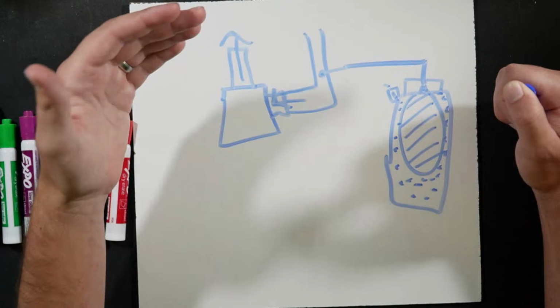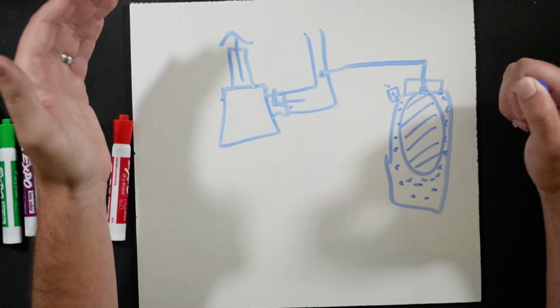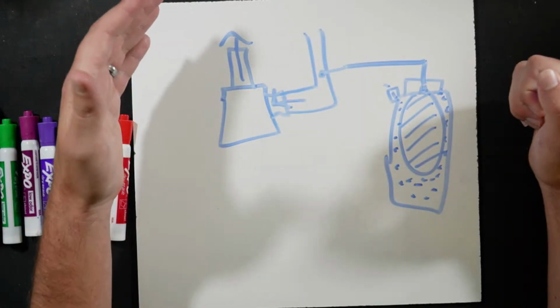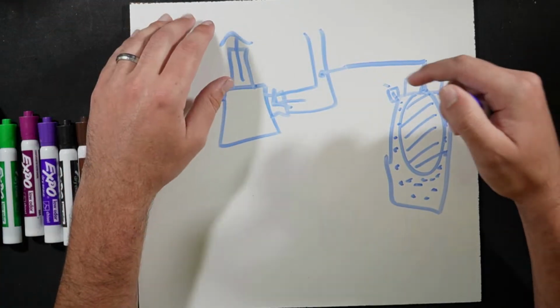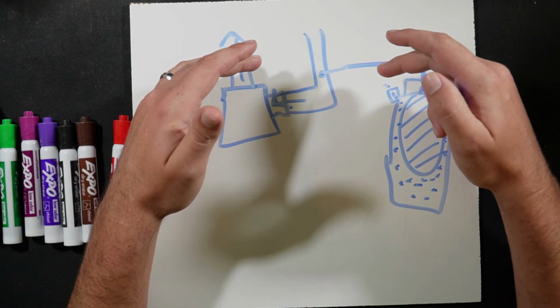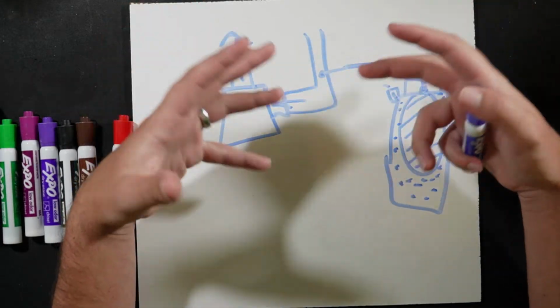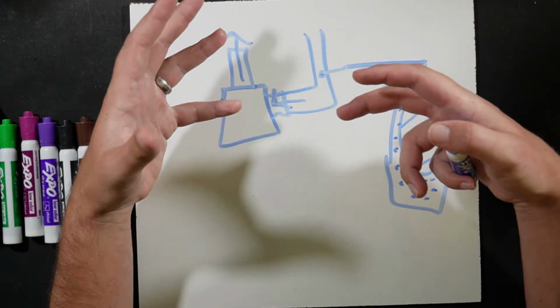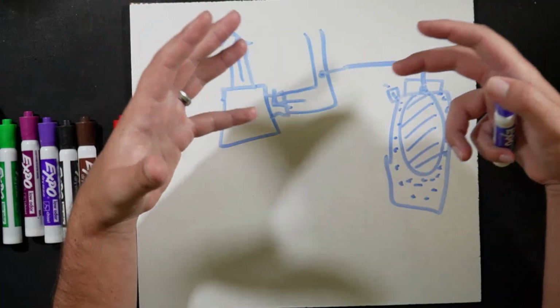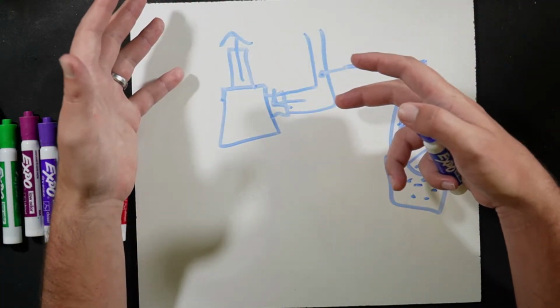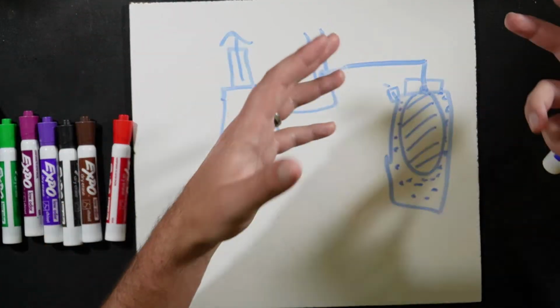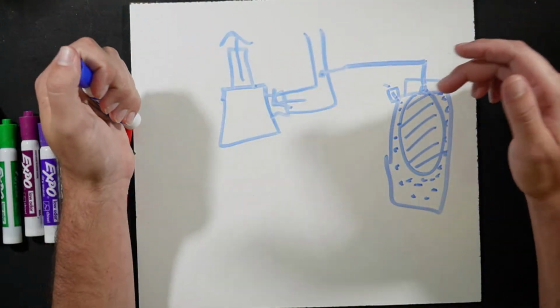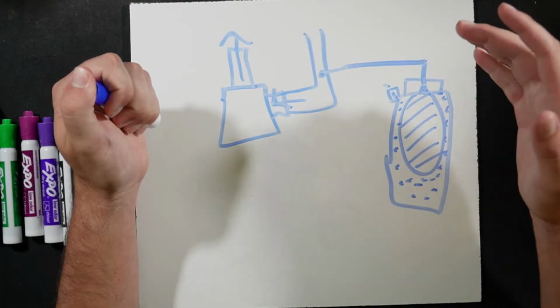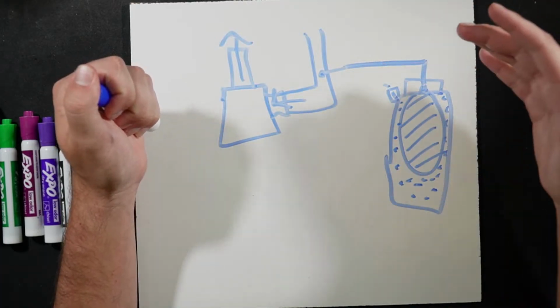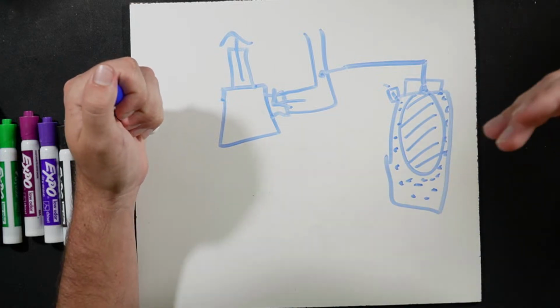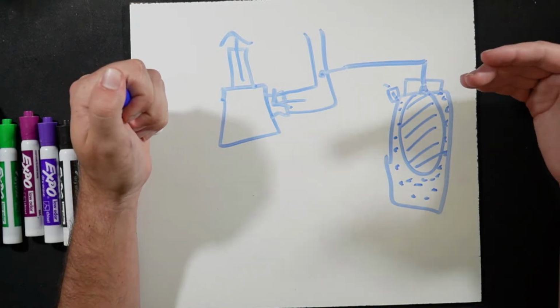This could be something as simple as an off cycle where we did a shutdown overnight. We come back on the next morning and we're processing the loop down. That whole process is going to cause a lot of pressure fluctuations due to the major temperature swings from the loop not being processed overnight to needing to get it processed the next morning. These bladder tanks help correct for that expansion, which is where the expansion tank concept comes from.